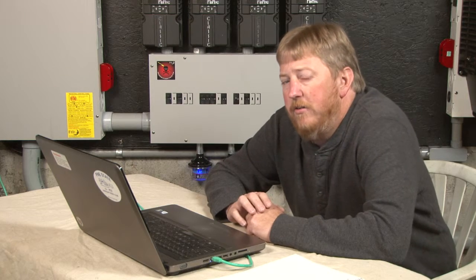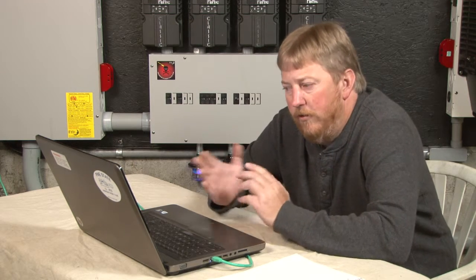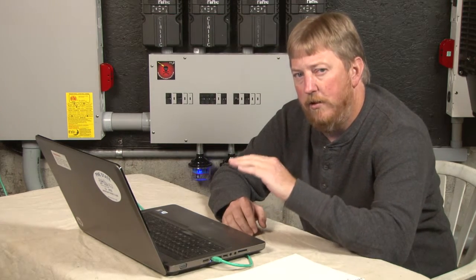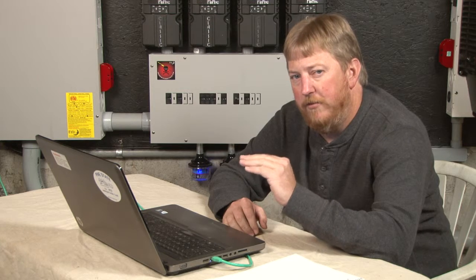Now, hypervoc is a non-operational safety zone. You'll notice you can click on the link there, and it will take you to a write-up about hypervoc. In my case, where I get really cold in the winter, it allows me to put a little bit more panel in series, and on those rare mornings when it does get that cold, we'll go up into the hypervoc region. The Classic will not turn on. It'll wait for the panels to warm up enough for that voltage to drop back down.